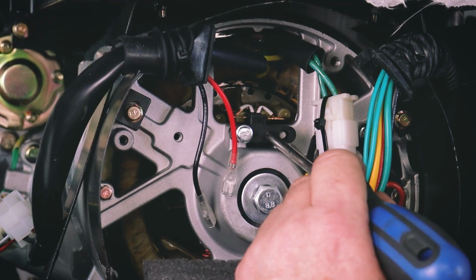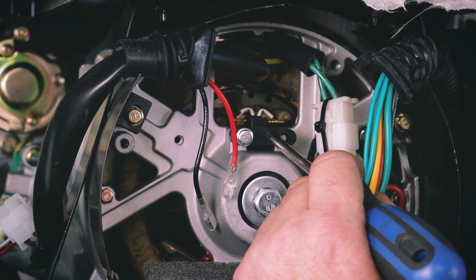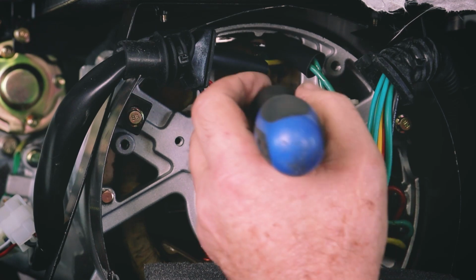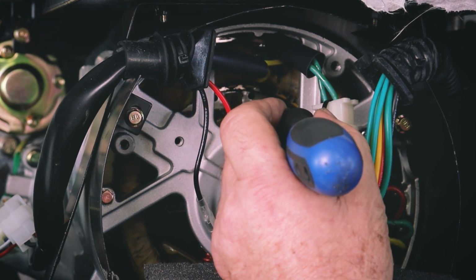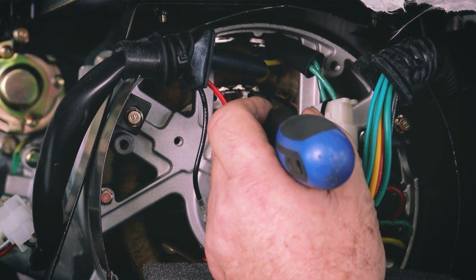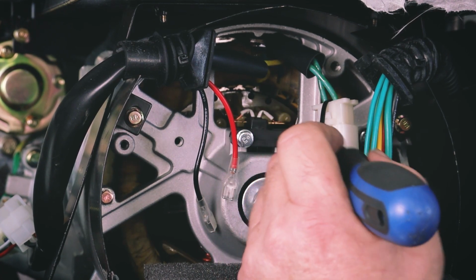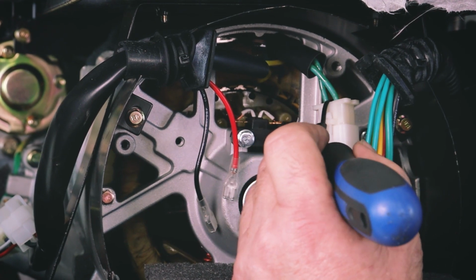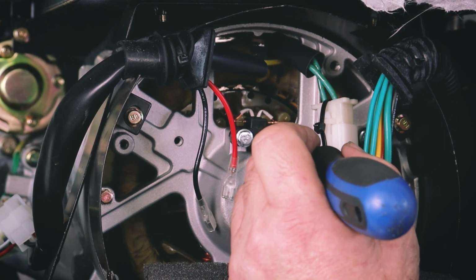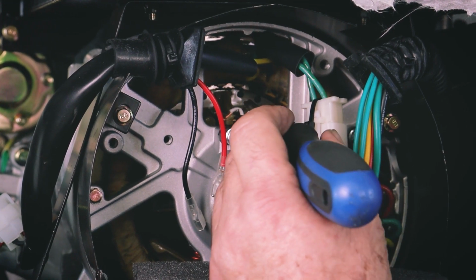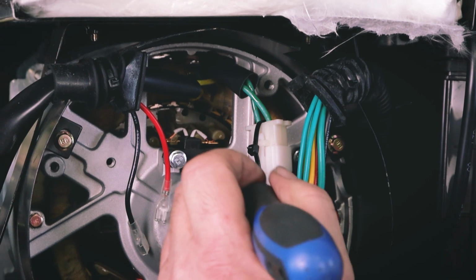Are the brushes worn out, or have the wires on the brushes broken? You can see these little red insulators on the top, and they're stuck up maybe 6 mil above the level of the top of this plastic. That's because the brush has quite a bit of meat left on it, and it's pushed back from the slip rings.